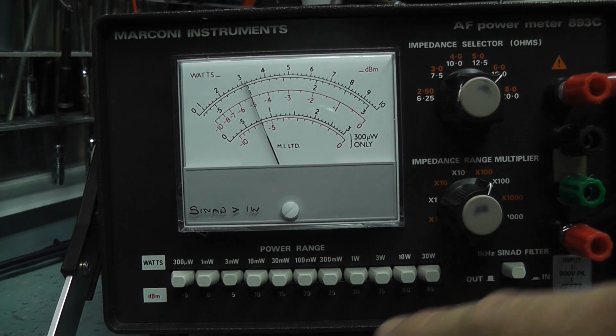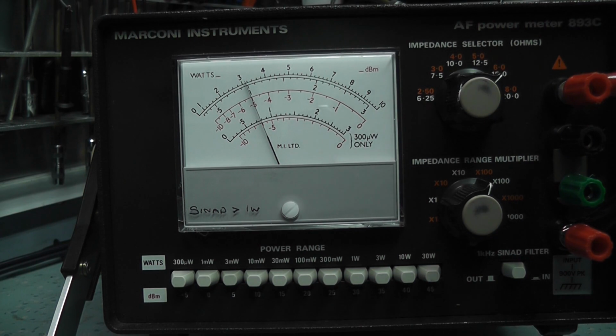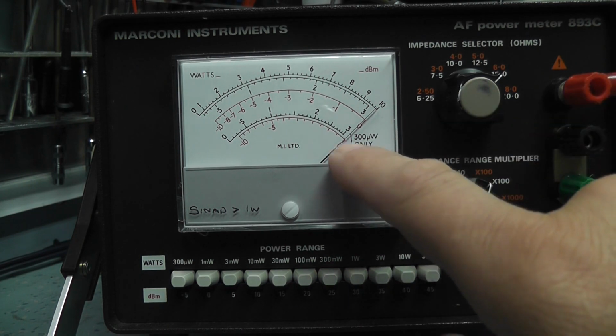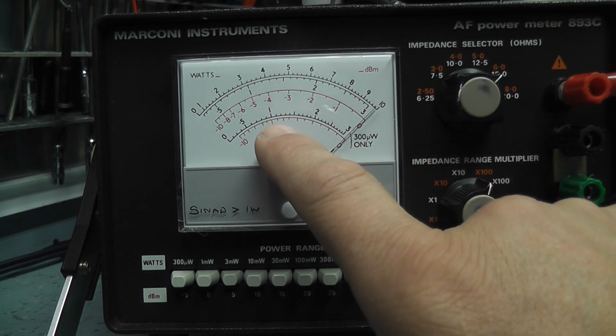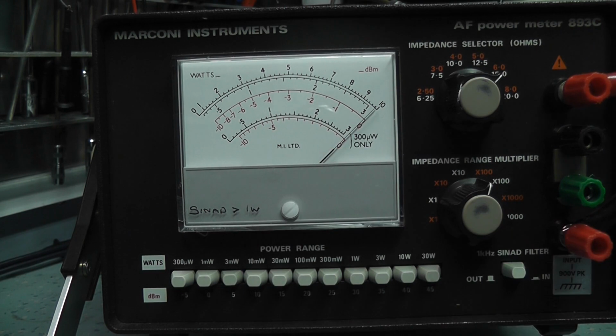I'll tell you what, I'm getting confused. So let's put 5 dBm in here. 5 dBm. So we've got full scale. So if I put 0 dBm, it should read -5, shouldn't it? 0 dBm. Yeah, and it's actually reading less than that. So I'm a bit suspicious of its accuracy there, but you know, it's within the ballpark. It's not hugely out. Let's go to another range.